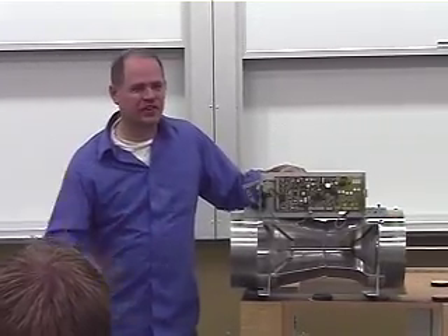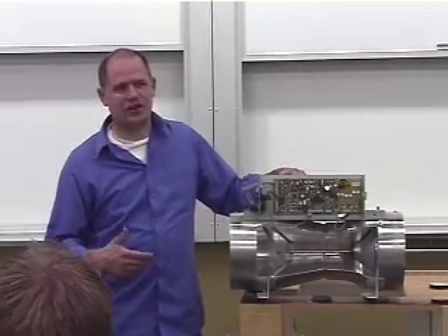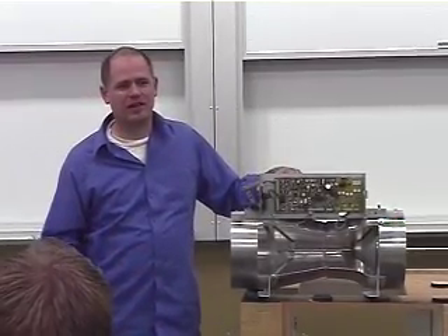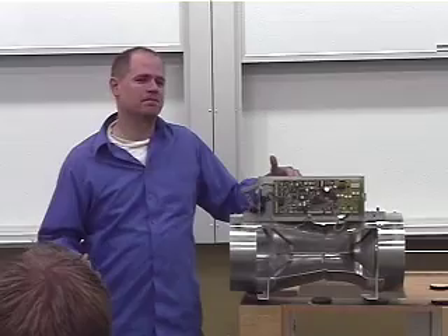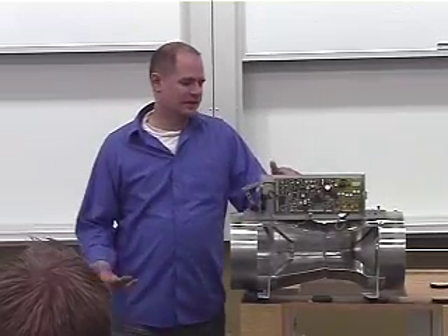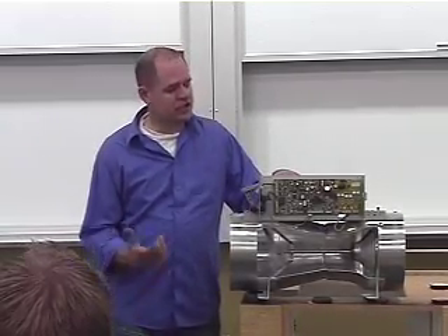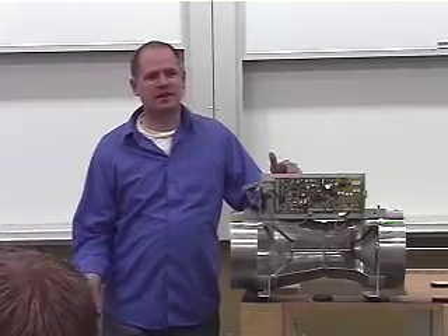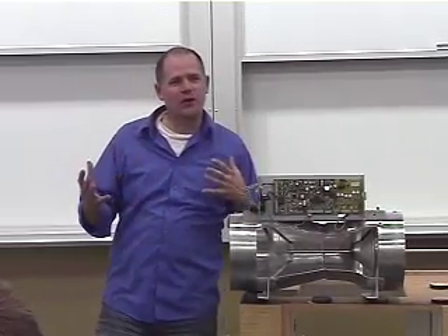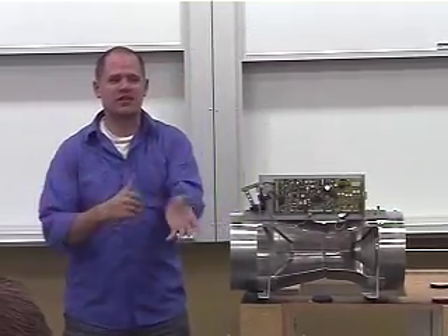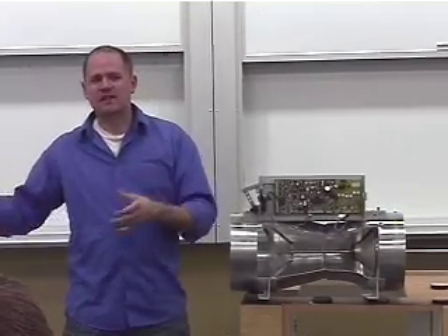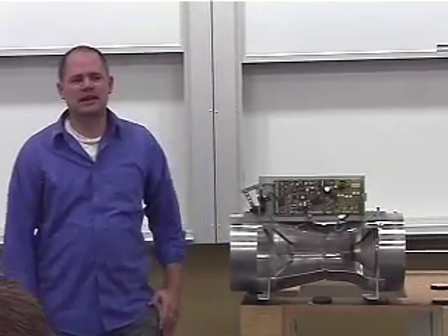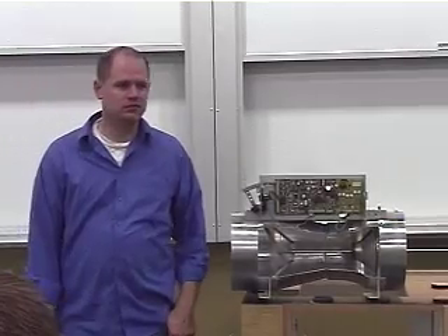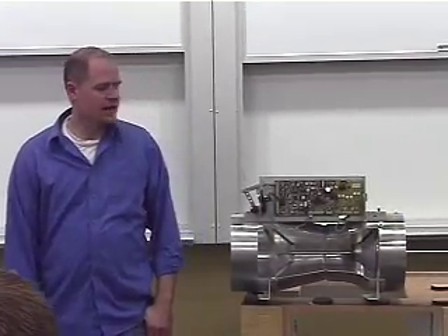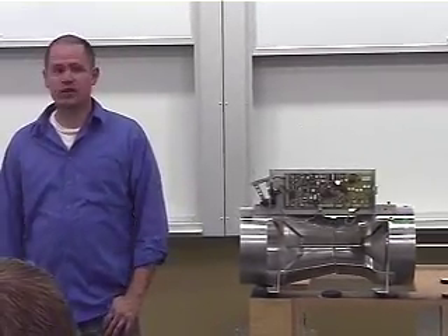Typically you'll see your whole system be low, and you'll have an alarm from your pressure in your ductwork before you would see a flow alarm. But it can be just one if for some reason it was designed with a certain scenario and all of a sudden they're taking more exhaust out in the middle somewhere, and that last one at the end of the line just doesn't quite get what it needed anymore. But that is correct. Any other questions?